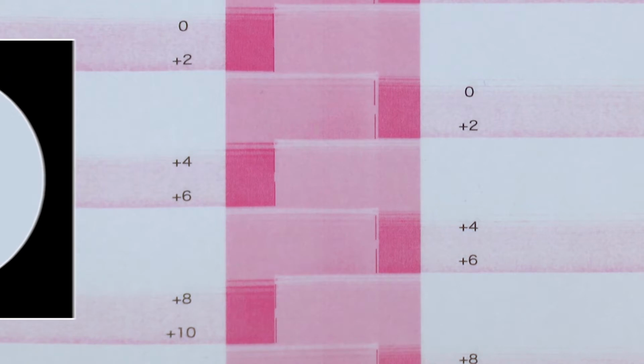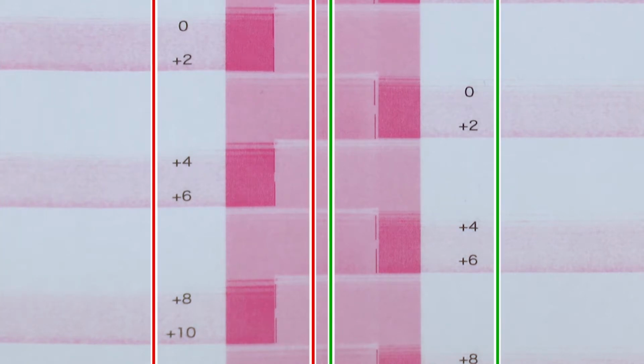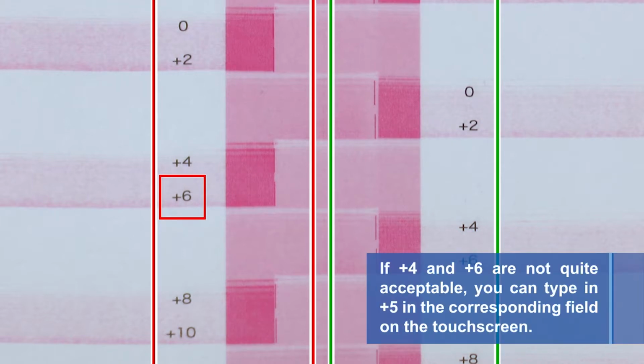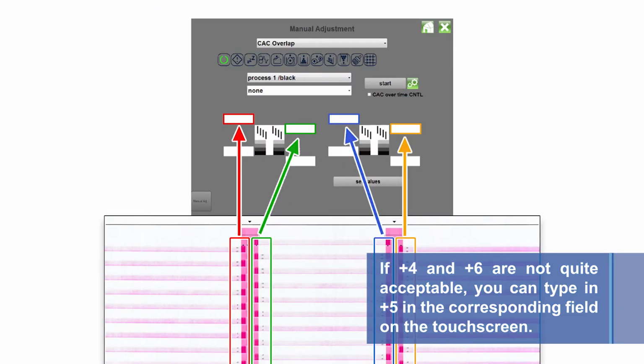With a loop, find the vertical line that touches the darker pattern but does not overlap each other. For example, the red area shows +6 as the best pattern. If +4 and +6 are not quite acceptable, you can type in +5 in the corresponding field on the touchscreen.